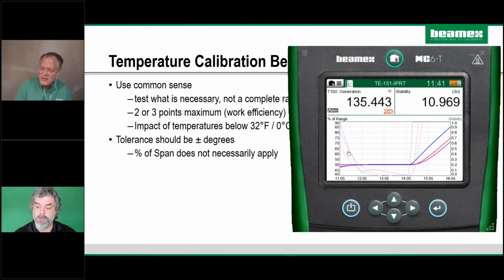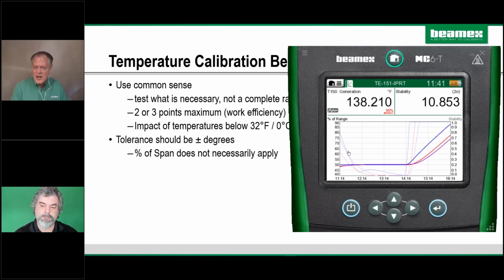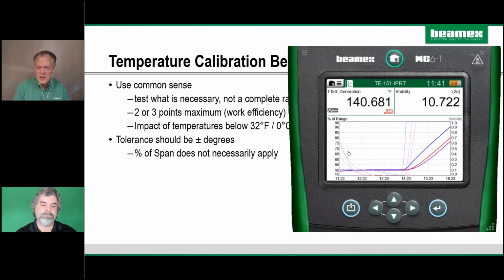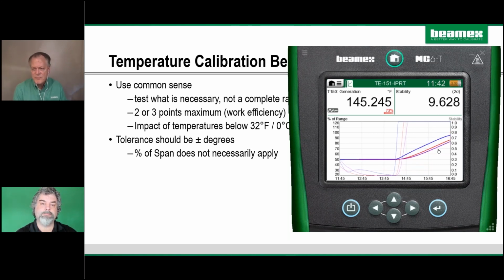But yeah, so there's just a lot in doing something like this, whether you're using a bath or a dry block. You really need to just understand what's going on in the background. What is this PID control doing? And here now we've got this stability component in the mix. But if you understand the dynamics of what's going on, the internal is always going to be the fastest response compared to anything else that you place in there, and you've just got to be patient. You can't rush through these tests, and you don't need to use a dry block for every temperature measurement in your plant.